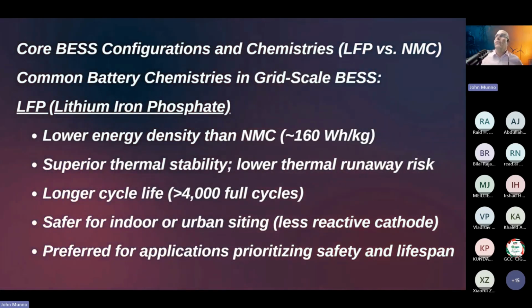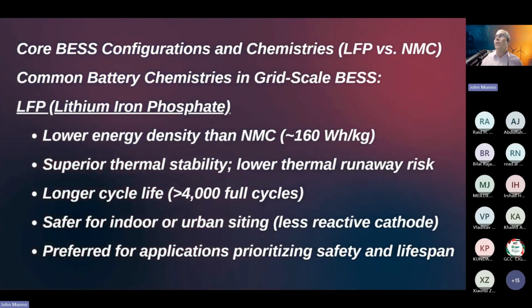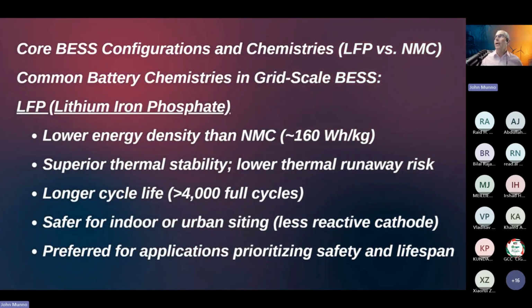The core configurations and chemistries. We hear of lithium iron phosphate, LFP, and nickel manganese cobalt. There's many, many other configurations, and today we're just going to talk about these two because this is what we see most installed right now. Starting with lithium iron phosphate, it's a lower energy density, so it won't have as much energy in a particular module as the same size nickel manganese cobalt would. However, they are superior in thermal stability. They have a lower thermal runaway risk. And it's not zero, but it's lower than with NMC.